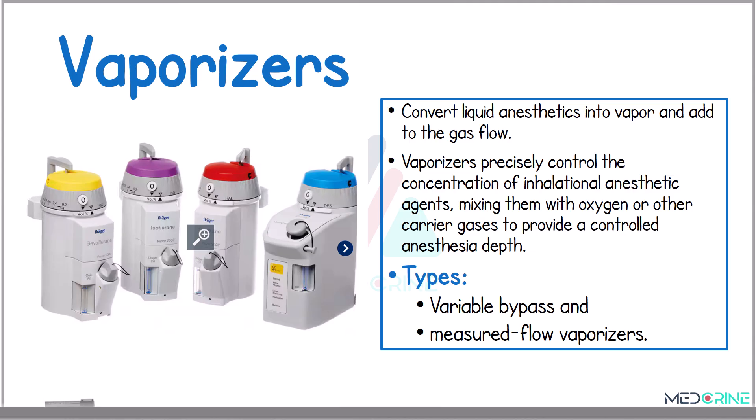Vaporizers convert liquid anesthetic agents, or volatile agents, into vapor and then add them to the gas flow. These vaporizers are designed to deliver a controlled concentration of anesthetic vapor mixed with oxygen or any other carrier gas. The types of vaporizers include a variable bypass vaporizer and a measured flow vaporizer, and for each of the inhaled anesthetic agents, the respective vaporizers are color-coded depending on the anesthesia.